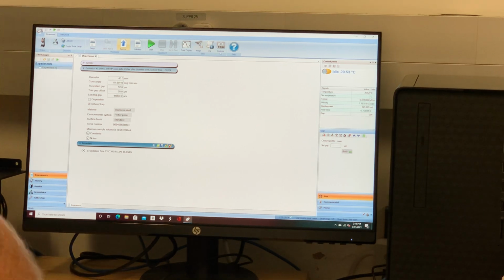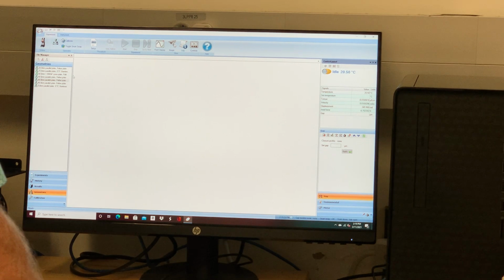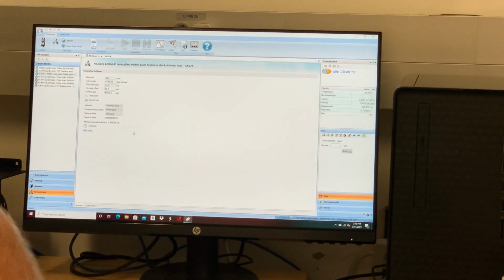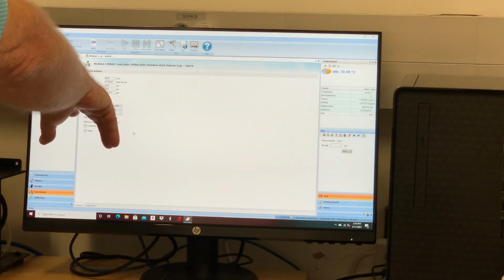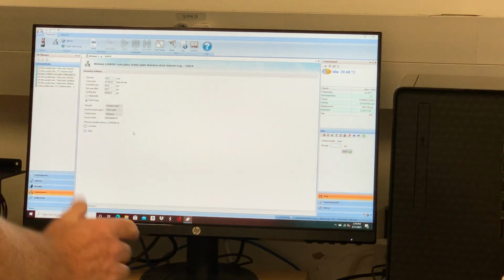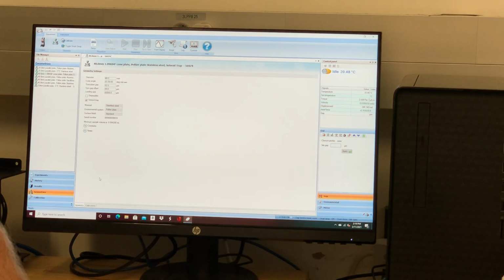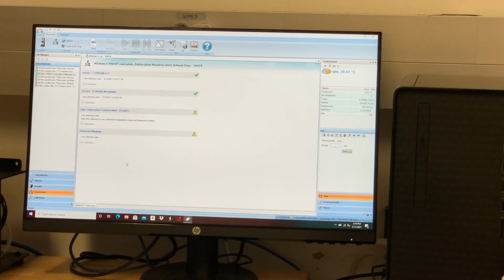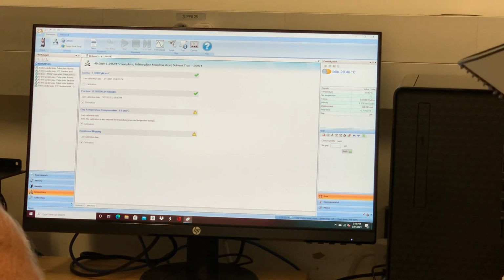So whatever geometry is right here is the active geometry. Okay? So now if we go over here to geometries, select the 40 millimeter 2-degree cone, it comes up with the geometry settings, so 40 millimeter diameter, it has the cone angle, all that stuff. And if we go down here, there's a tab that says calibrations. And these are the other calibrations you're going to be concerned about, okay?